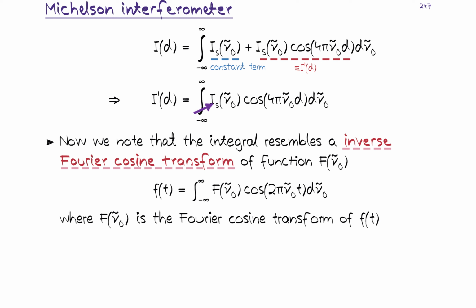And what this means is that really physically with these kind of devices, we can measure the interferogram, so that I(d) function, so essentially we are measuring irradiance of light as a function of this d parameter. So essentially we are detecting light for a given mirror position. We measure the irradiance and we record the value. Then we move the mirror slightly, and then we record the changed irradiance pattern. And then we move the mirror position even slightly more, and we are again measuring the irradiance pattern. And this is how we can physically measure this thing known as the interferogram.